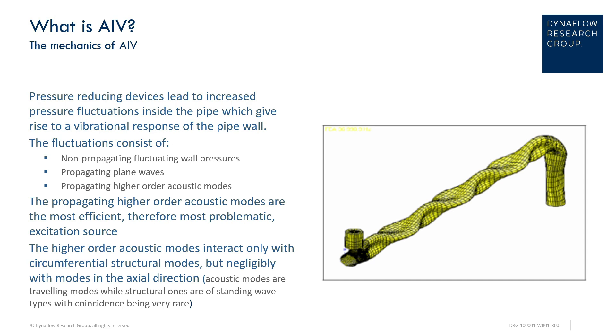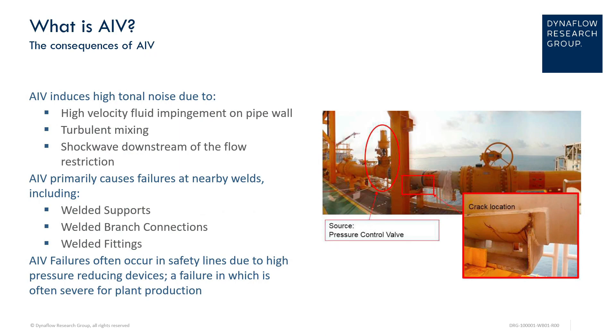These acoustic modes are also travelling modes that interact only with the circumferential structural modes. AIV generates high tonal noise levels through high-velocity fluid impingement on the pipe wall, alongside turbulent mixing and shock waves downstream of a flow restriction.